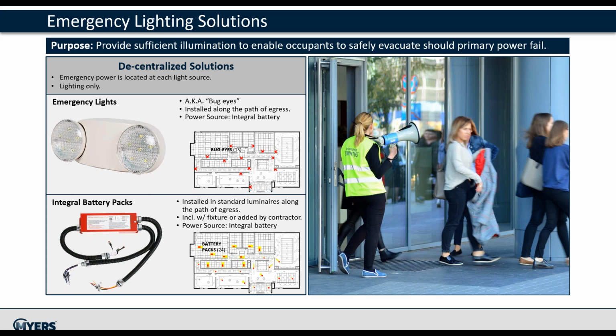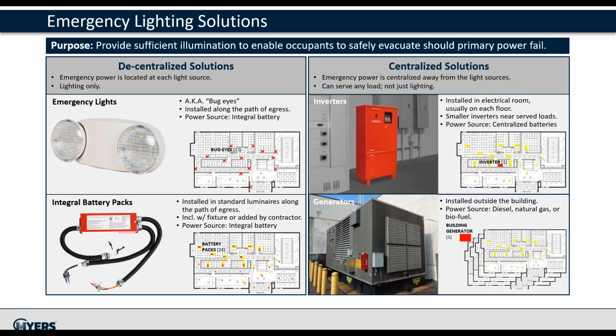Integral battery packs are installed in the fixtures and provide a portion of the full light output to illuminate the path of egress. The second classification are centralized solution that consists of inverters and generators. The term central is defined as a local power source serving a number of fixtures. Inverters can be located just about anywhere inside or outside the building: control rooms, closets, basements, ceilings, mezzanines. Typically, the smaller sized inverters are located near the served loads, and larger systems are located in dedicated power rooms. The power source for emergency operation is batteries.